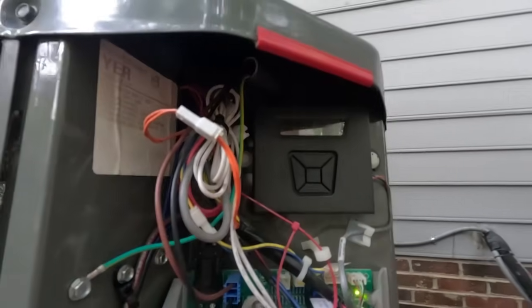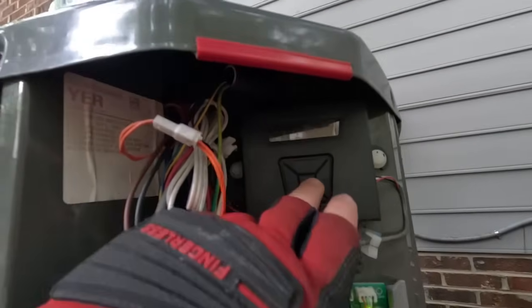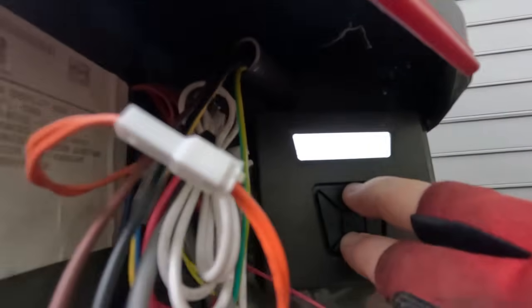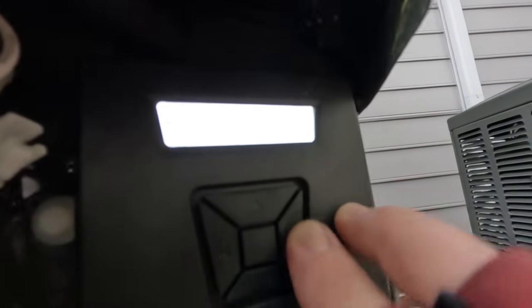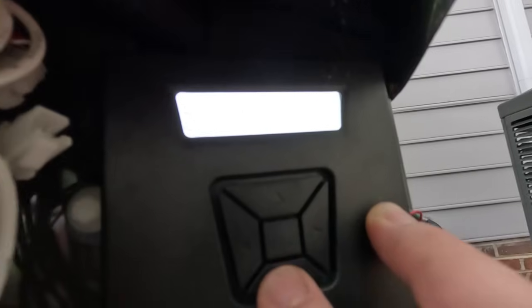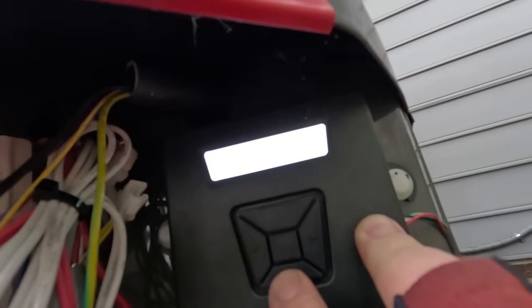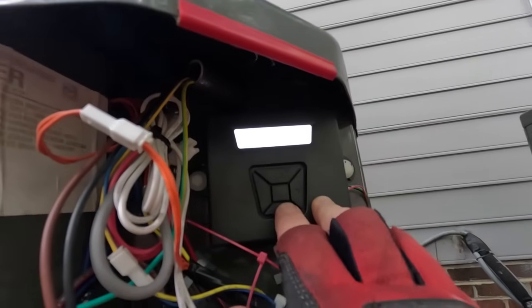So this thermostat just started calling. So let's go in here real quick and hold these two buttons down for about 10 seconds, and then you can go into your menu, and then once it shows monitor, I don't know if you can see that or not, scroll down to system, then scroll over one, then scroll down. It gives you your compressor speed, and you're in cooling mode. Load shed's not hooked up, so it's showing 72 degrees as our ambient, which is about what it is. I got 71 out here right now. It's finally cooled off, thank goodness. The humidity's dropped, the heat is gone for a little bit of a break this week. And our suction temperature sensor is now showing 64 degrees.